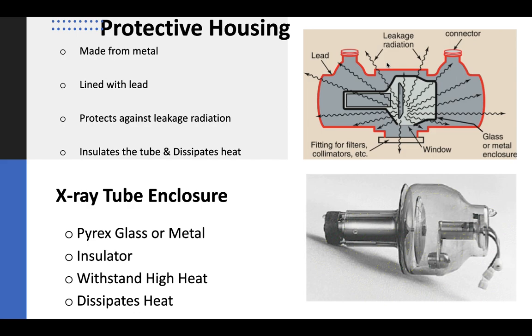The protective housing helps to insulate the tube. It includes a cooling fan, which helps dissipate heat. The X-ray tube enclosure: metal enclosures are more commonly used today due to their superior electrical properties. The enclosure acts as an insulator and helps to dissipate heat. It eliminates air from being inside the tube, and if the enclosure gets too gassy, it has a direct effect on electron flow, resulting in fewer X-rays being produced and tube failure.